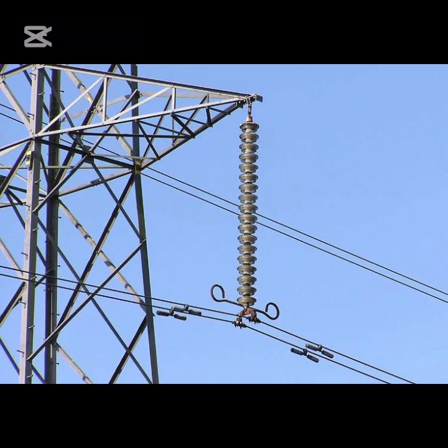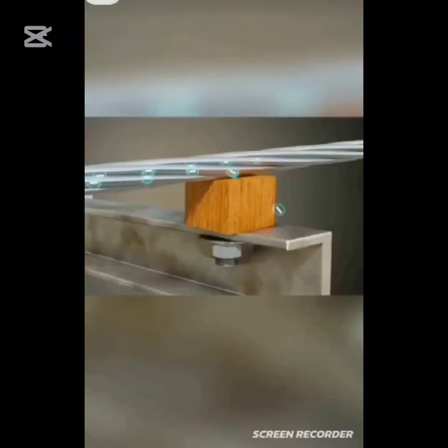Why are conductors in high voltage transmission lines placed far from the support structure? At high voltage, the air molecules surrounding conductors become ionized, compromising the insulation properties of the air. This breakdown can cause the air molecules to conduct electricity, leading to a discharge to ground through nearby support structures.